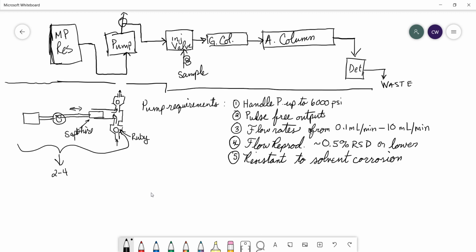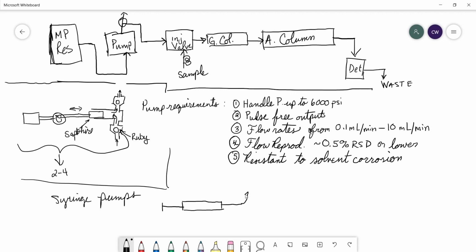There are also other kinds of pumps rather than a simple reciprocating pump. You can have syringe pumps. These have a physical glass syringe, sometimes plastic, that is connected to your system, and the plunger is controlled by a stepper motor. So there is a physical motor that depresses the plunger in the syringe, which gives you a steady input. Syringe pumps are typically not used for very large flow rate systems because you still need a regular pump to deliver this constant flow to get your chromatography going. Syringe pumps are typically used more for controlled sample introduction into a flowing stream.